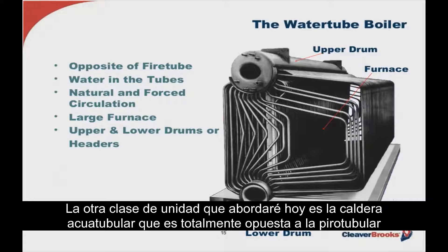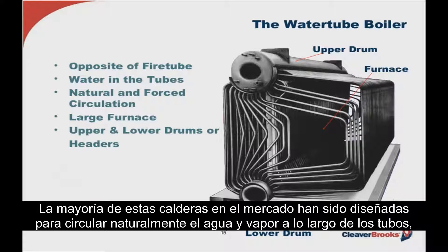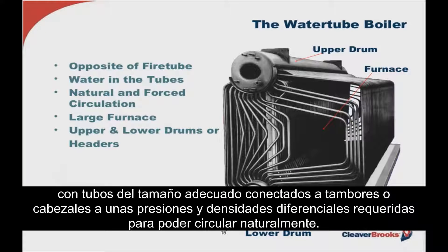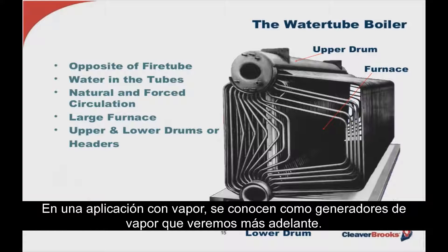The next major design category is the water tube, which is just the opposite from the fire tube: the water is in the tubes, and the fire and hot gases surround them. Many water tube boilers today have been designed to naturally circulate the water-steam combination through the tubes, utilizing properly sized tubes connected to drums or headers to provide the pressure density differentials required for natural circulation. However, there are other water tube designs which require forced circulation, incorporating their own pump — in a steam application, often referred to as steam generators.